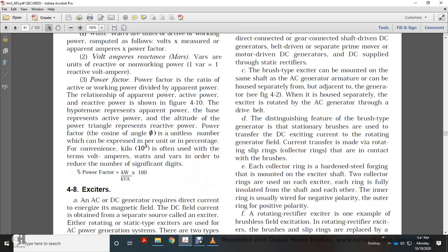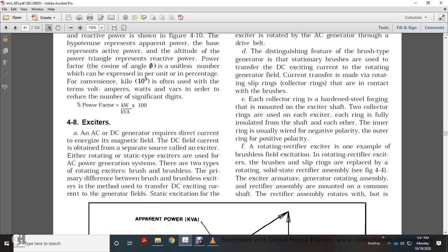Each collector ring is a hardened-steel forging that is mounted on the exciter shaft. Each ring is fully insulated from the shaft and from the other rings. Usually the inner ring has negative polarity and the outer brush ring has positive polarity.